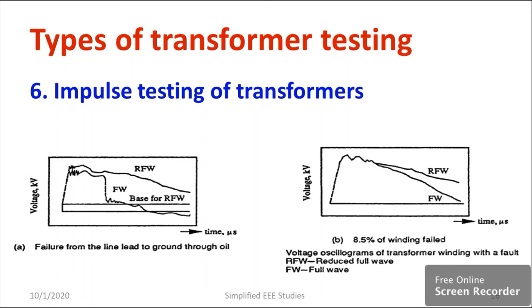By looking at the waveforms, we will come to know if there is any deviation happening in the transformer oil. These are the basic inferences we can make from impulse testing. If you observe such waveforms, the first type is failure from the line lead to ground through the oil — the transformer oil has to be replaced. Regarding winding insulation, if there is a problem, the full wave will droop down — that's the peculiarity.